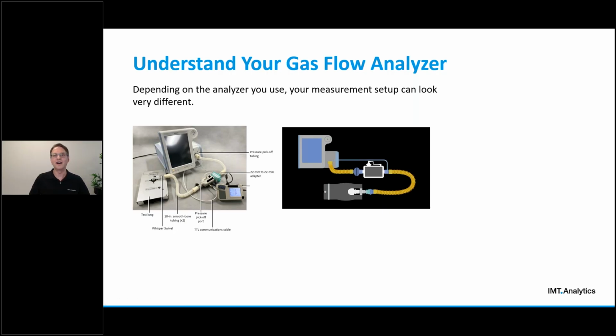Often you will also find setup-related considerations in the user manual of the analyzer. So make sure you know how your gas flow analyzer measures the relevant parameters, and check the user manual for setup-specific information. It is really crucial to understand, for example, what is being measured inside the flow channel of your analyzer, and maybe even more important, what is not, because wrong setups can really lead to significant measuring errors.